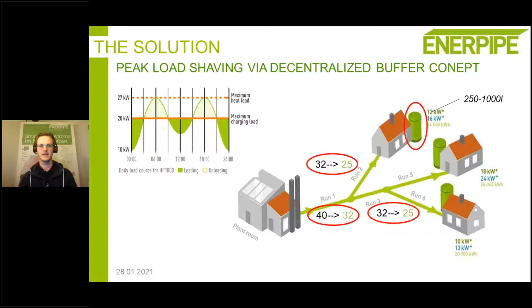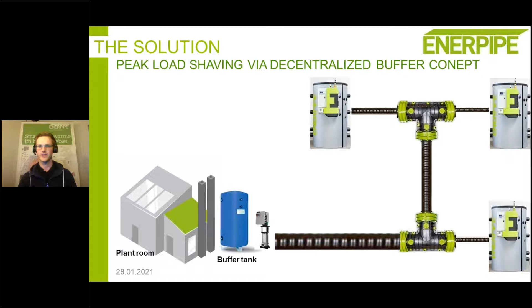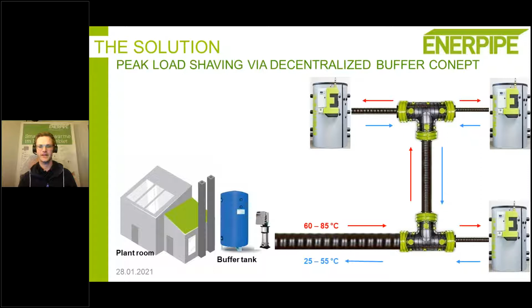Here I can explain it again. Normally you have the plant room, a buffer tank, a pump, and the pipes. You want to transport the hot water to the houses with a plate heat exchanger, but instead of the heat exchanger, we quite often install this kind of decentralized buffer tank. The temperatures depend on the kind of houses which are connected. So the flow temperature is quite often between 60 and 85 degrees in our projects. Of course, in big inner city networks, you quite often have higher temperatures, higher than 100 degrees. And the aim is to achieve very low return temperatures, and with our system we can achieve temperatures in the area of 30 degrees.